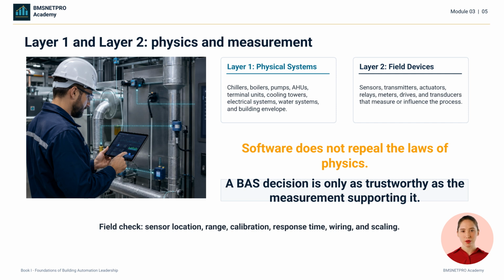Layer 1 is the physical building: chillers, boilers, pumps, air handling units, terminal equipment, electrical systems, and the building envelope. This layer is governed by thermodynamics, fluid mechanics, heat transfer, electrical principles, equipment limits, and the actual site conditions. Layer 2 is measurement and actuation. If a sensor is in the wrong location, out of calibration, slow to respond, wired incorrectly, or scaled incorrectly, the BAS may respond perfectly to bad information.